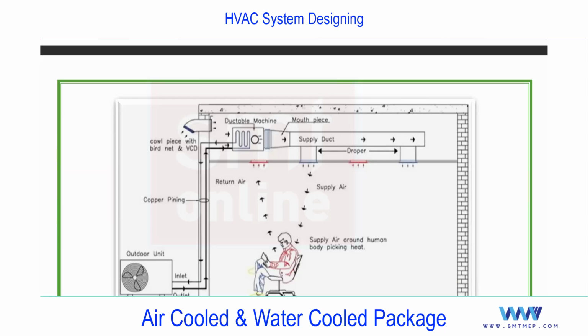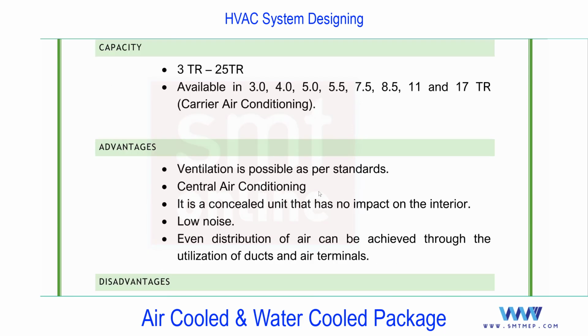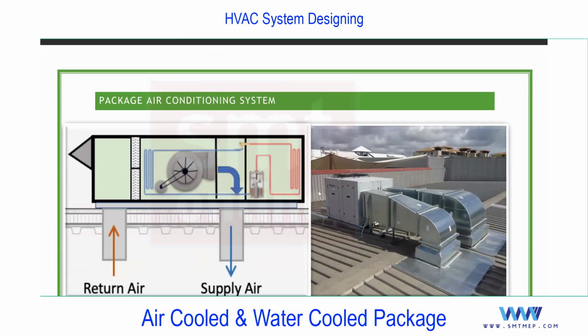So what will happen in this case? This complete area above the false ceiling, we used to call return air plenum. And this is called free return. Anyhow, this suction is above the false ceiling. But if I place this complete unit outside, it means return is required from the space where you are supplying. Okay, so for an air-cooled package, remember, a return air duct is required.